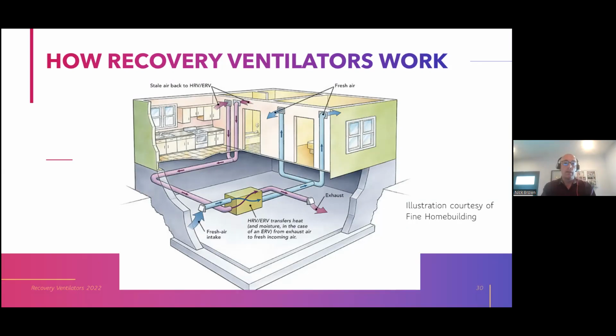The exhaust air is being expelled from the house here through this pink duct, another penetration through the building envelope. And you can see it's bringing in exhaust stale air from the kitchen and a bathroom in this picture. And in the core here, we're swapping the heat and or the moisture of those air streams, but without mixing them. So if you've got a cooking odor coming in the exhaust from the kitchen, you don't need to worry that that's going to show up behind closed bedroom doors. The air streams don't cross, they just swap heat and or moisture.